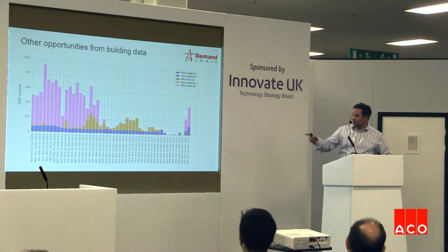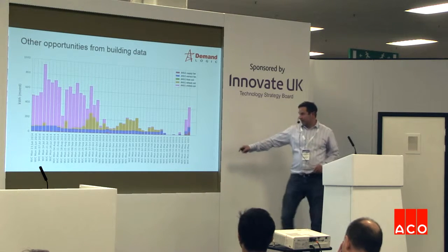This is virtually a year. This is a real example. This is where you can see on the right-hand side here, this is where an energy conservation measure was carried out, and the output of that unit dropped down dramatically, but then it experienced slipback, which is extremely common. Something happened in the building subsequently that was unexpected. So a lot of effort was put in to make that unit save energy, and suddenly it went haywire. What we're saying here is that you can use the same principles of metering just by using the raw data that you have.